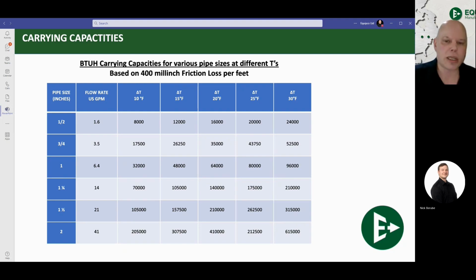And this is not to say that the 1.25 inch piping is going to be required throughout the entire system. We just need that for our mains. Maybe off of our mains, we're going into this branch over here, which is 10,000 BTUs, which only requires ½ inch. And this branch over here, which is your indirect, which requires 60,000 BTUs, which we can use 1 inch. So there's all sorts of different ways to extrapolate which pipe size you want to use. It all just basically depends on what exactly you are doing in your system, and use this chart to help you to size that piping properly.